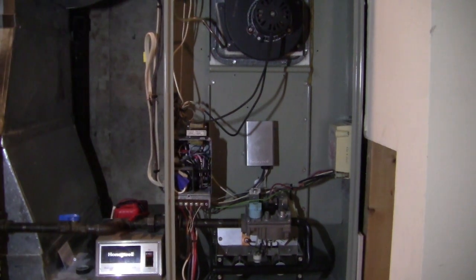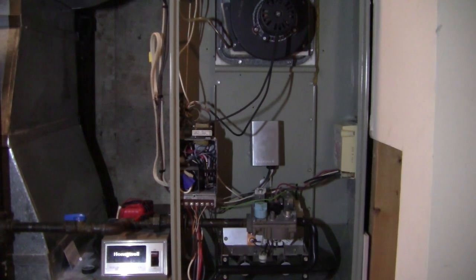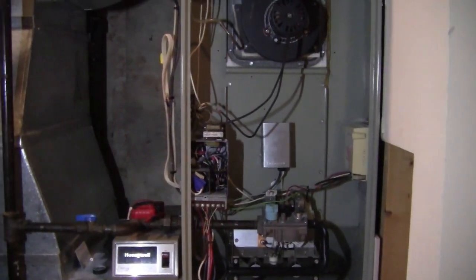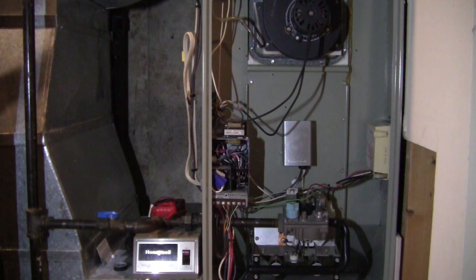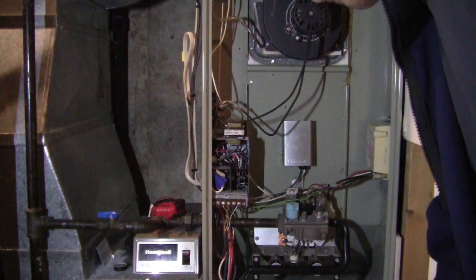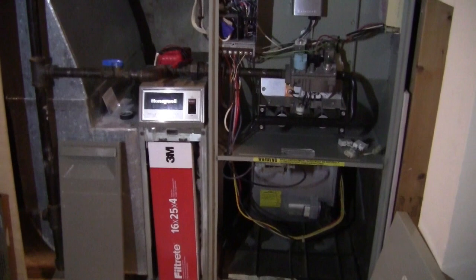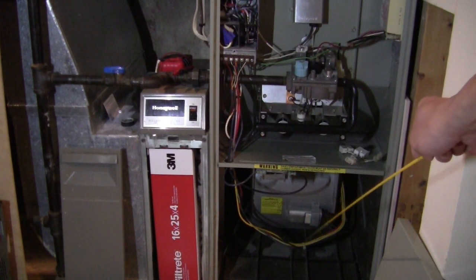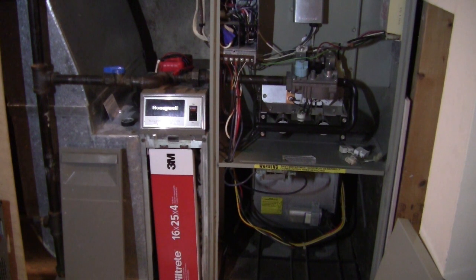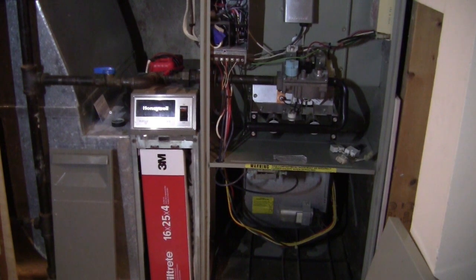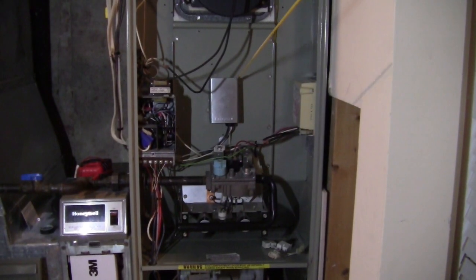Okay, now how does the controller prevent problems when people don't change the filter and something happens to the fan? The main fan down here is broken. If the fan is not running, if the fan is clogged, or the fan has some electronic issue, it just runs not efficiently, runs slow. How can the controller prevent this kind of issue? There is something we can identify inside the chamber, right?